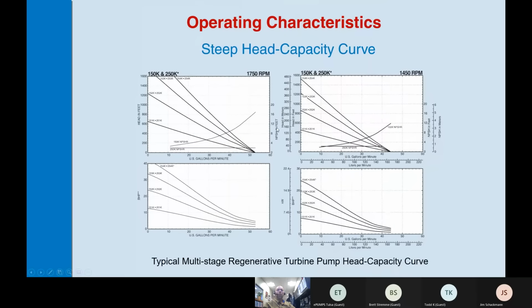As you can see from the sample curves that I have on here, we have some of our C series, which are centrifugal pumps, where we can go out to 100 gallons a minute, but only hit about 60 feet of head, and that's a 4-inch centrifugal, where with our 4-inch regen turbine, we're only doing maybe about 20 to 25 gallons per minute, but we're all the way up at 600 feet of head. So the steep head capacity is the main characteristic of a regen turbine.